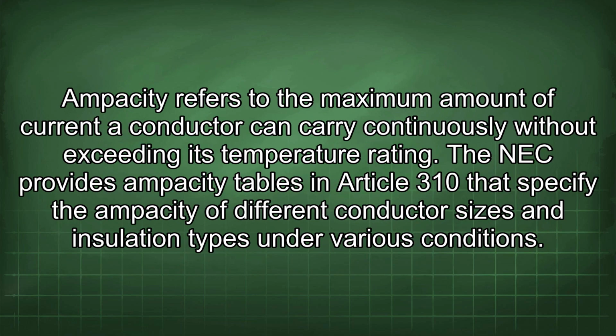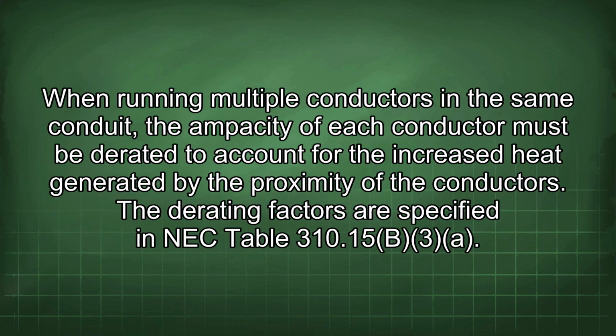Ampacity refers to the maximum amount of current a conductor can carry continuously without exceeding its temperature rating. The NEC provides ampacity tables in Article 310 that specify the ampacity of different conductor sizes and insulation types under various conditions. When running multiple conductors in the same conduit, the ampacity of each conductor must be derated to account for the increased heat generated by the proximity of the conductors. Derating factors are specified in NEC Table 310.15(B)(3).